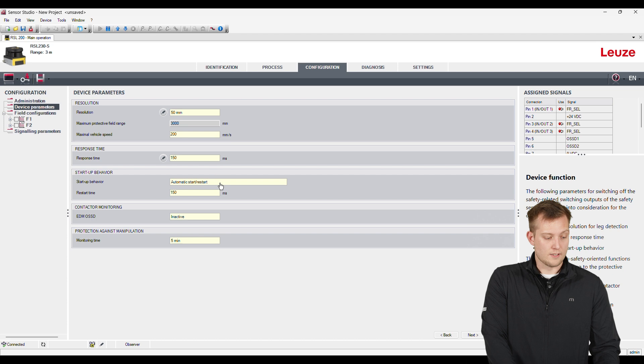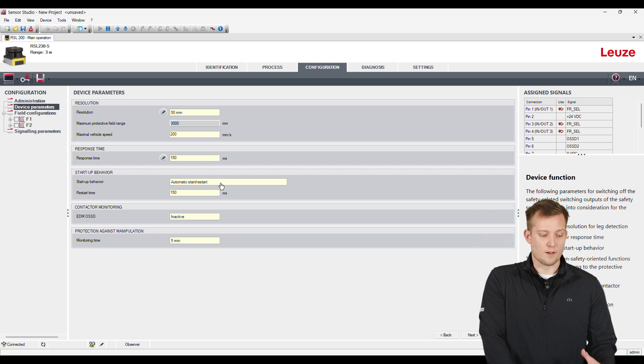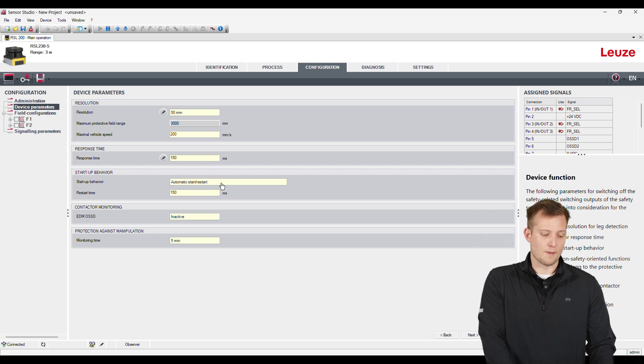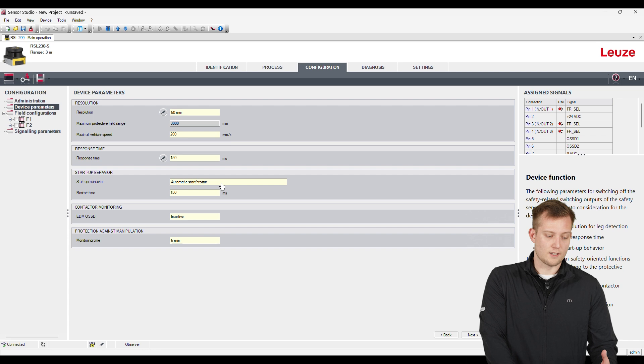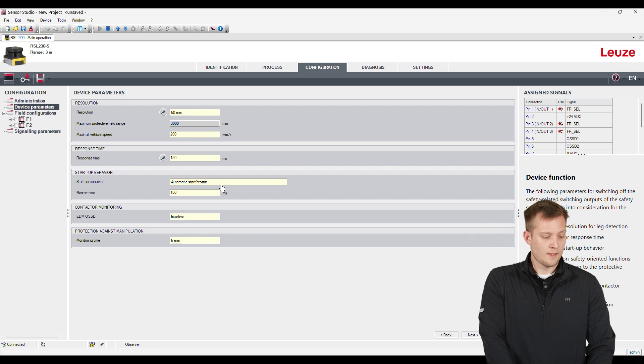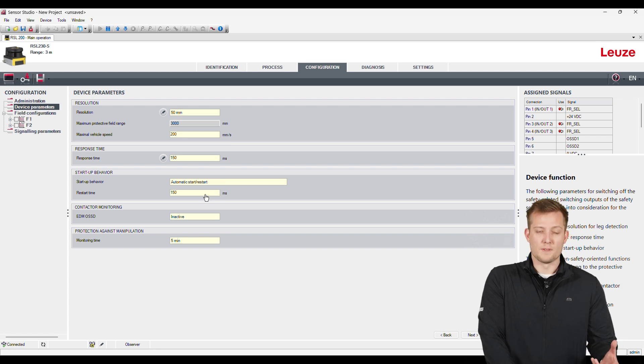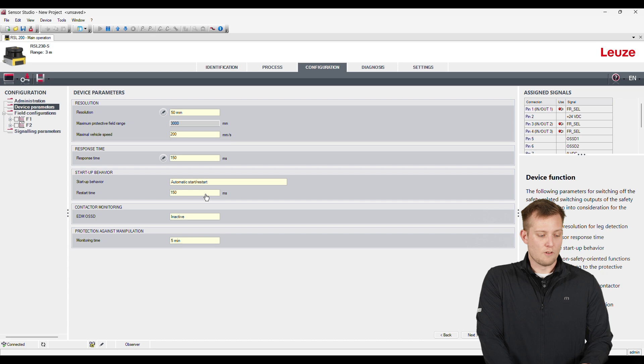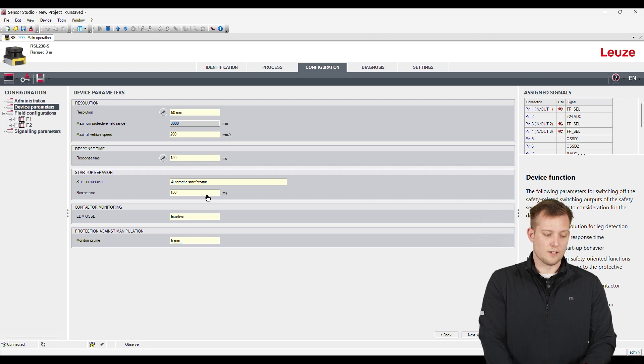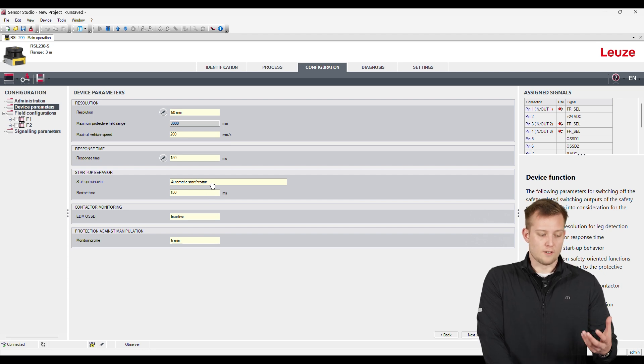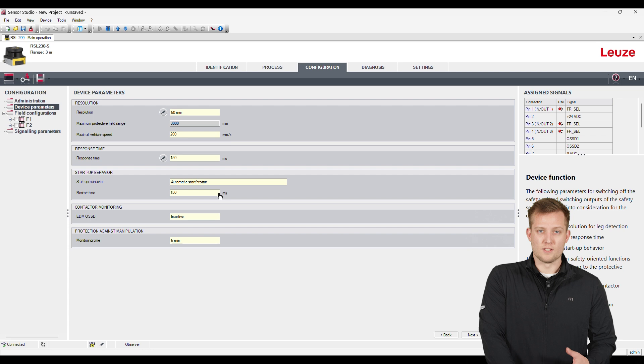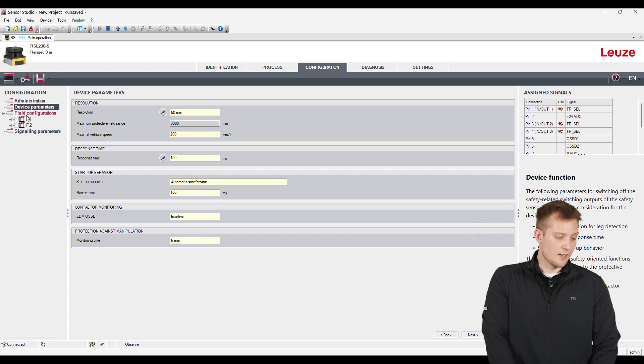And then right here is the start behavior. So I have it set up in an automatic restart. So if you wanted to have a manual restart, we can adjust that and change that there. And then the restart time. So restart time is going to be, once the sensor is clear and ready to go, it's going to take 150 milliseconds for the sensor to fully reboot again.